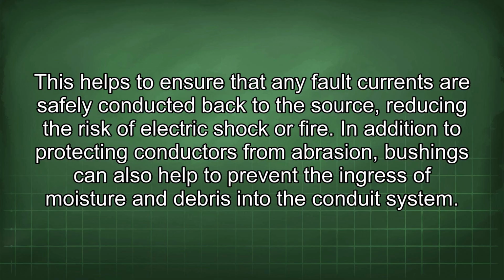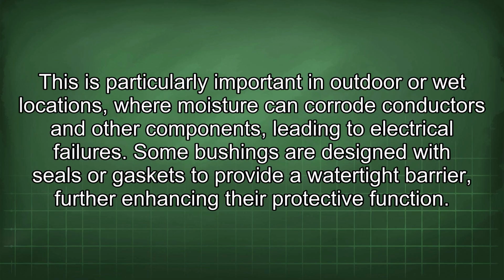shock or fire. In addition to protecting conductors from abrasion, bushings can also help to prevent the ingress of moisture and debris into the conduit system. This is particularly important in outdoor or wet locations, where moisture can corrode conductors and other components, leading to electrical failures. Some bushings are designed with seals or gaskets to provide a watertight barrier, further enhancing their protective function.